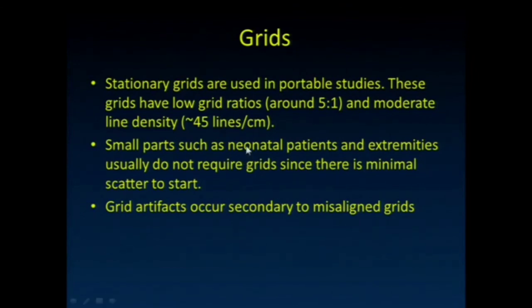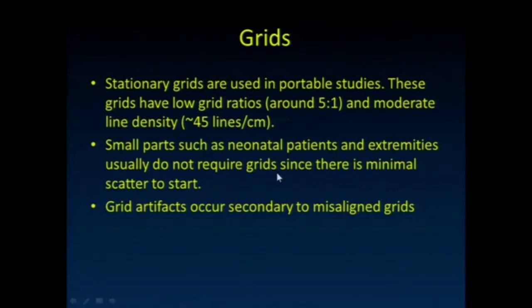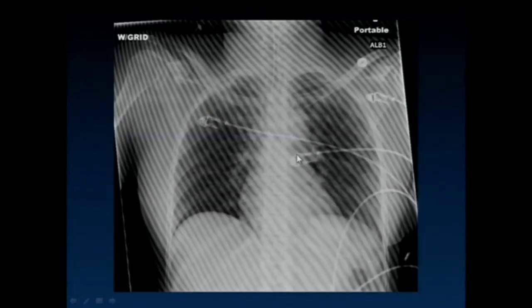For portable studies, stationary grids are used, and they have lower grid ratios and moderate line density. Sometimes you can see the grid pattern on portable studies if they're not placed very well. We already mentioned that small parts and neonatal patients don't require grids because there's minimal scatter to start with — we certainly don't want to put a grid in there because it will increase dose when we didn't need the grid in the first place. And here's one of those misaligned grids that you'll see sometimes — this one's really prominent.